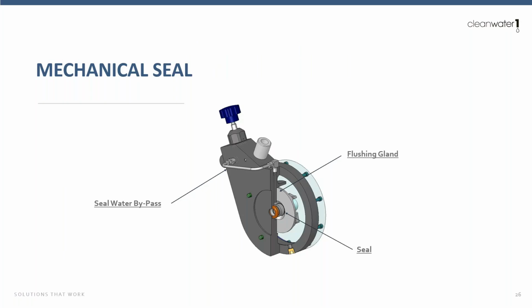So there's a couple different options for this. Some of these systems have what's called a seal flushing system. So it'll automatically flush the seal anytime the polymer system is in operation. But I always recommend, as far as spare parts for these polymer systems go, to have an extra mechanical seal on the shelf. We'll get into it here in a second, but flushing and cleaning is really important to help remediate the issues with the mechanical seal as well.